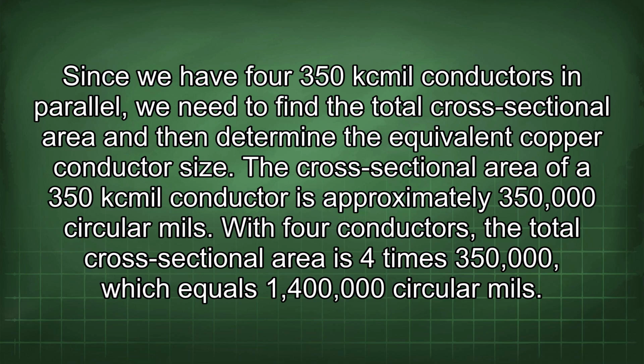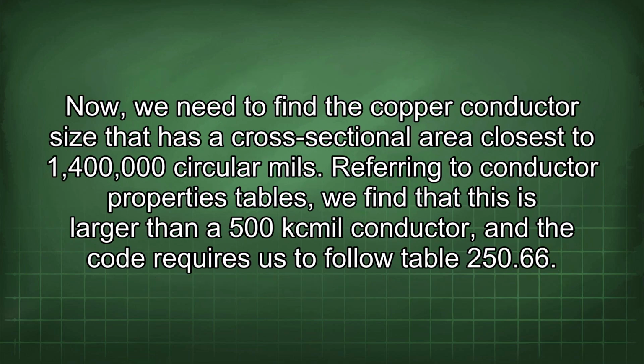The cross-sectional area of the 350 kcmil conductor is approximately 350,000 circular mils. With 4 conductors, the total cross-sectional area is 4 times 350,000, which equals 1,400,000 circular mils. Now, we need to find the copper conductor size that has a cross-sectional area closest to 1,400,000 circular mils.